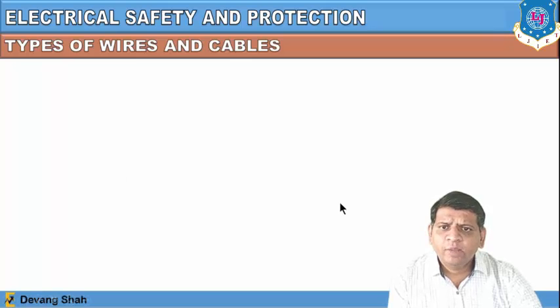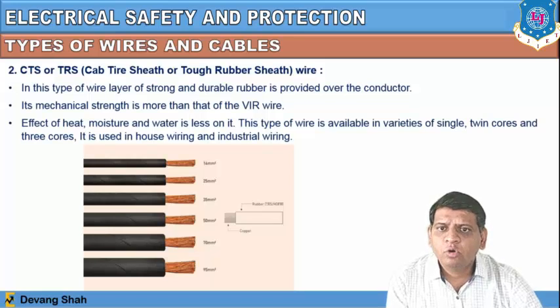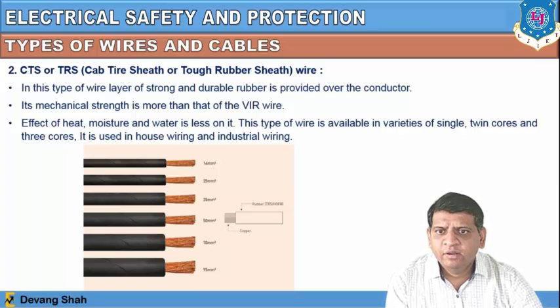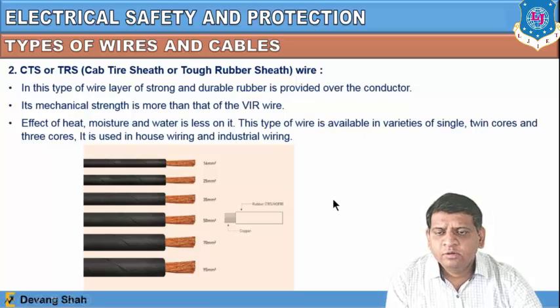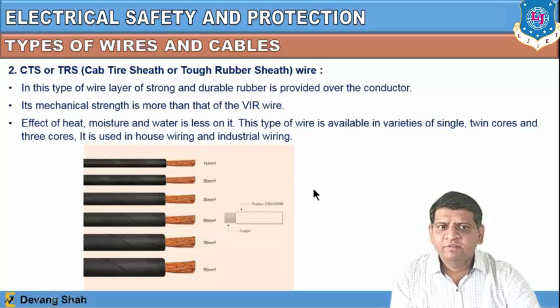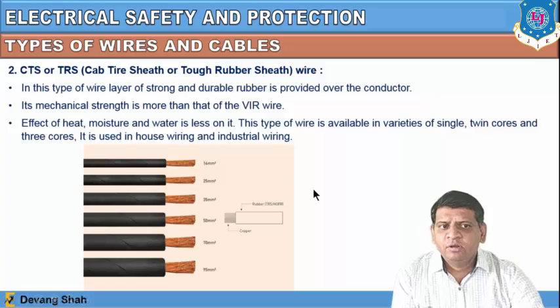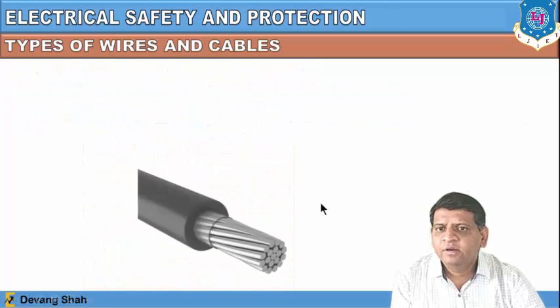Another type is CTS or TRS — cab tyre sheath or tough rubber sheath wire — where a layer of strong and durable rubber provides greater mechanical strength than VIR wire. The effect of heat, moisture, and water is less on it. This type is available in single, twin core, or multi-core varieties and is used in house wiring and industrial wiring.